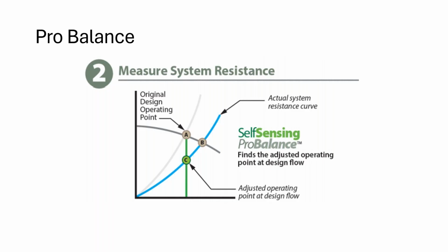But anyways, once you do the right keystrokes, you put it in constant flow mode and say, I want to run it at 300 GPM, and you let it run for a little bit, and the system is going to display on there the actual head loss of the system. All right, so in my example, it was 300 at 50. Maybe it's running in at 300 at 40.